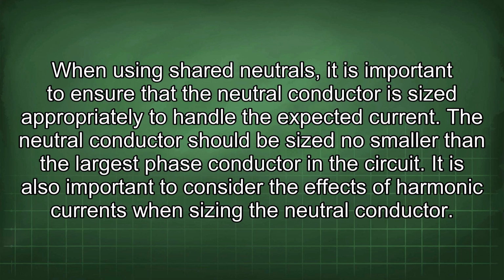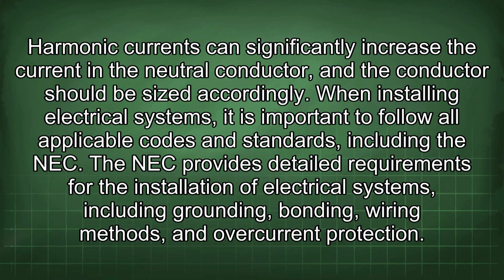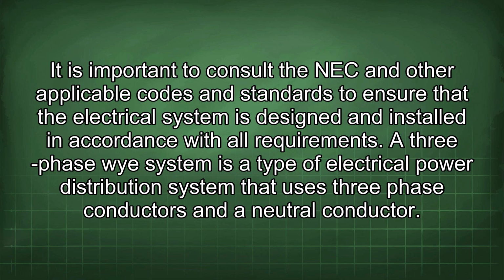It is also important to consider the effects of harmonic currents when sizing the neutral conductor. Harmonic currents can significantly increase the current in the neutral conductor, and the conductor should be sized accordingly. When installing electrical systems, it is important to follow all applicable codes and standards, including the NEC. The NEC provides detailed requirements for the installation of electrical systems, including grounding, bonding, wiring methods, and overcurrent protection. It is important to consult the NEC and other applicable codes and standards to ensure that the electrical system is designed and installed in accordance with all requirements.